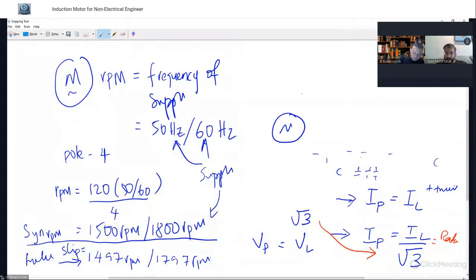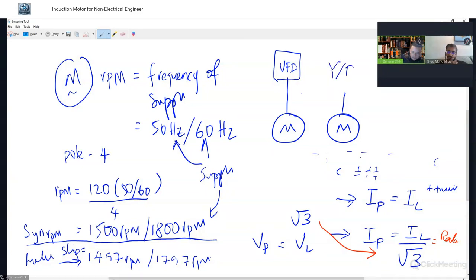Now, if you have motors here, you are going to connect your VFD here, right? Now imagine, the question just now, how are you going to connect star delta and VFD together to the motors? So it's not possible, right? Because the connection over here, the interface to the motor, is actually one only. So you have to connect either to the star delta, which requires 6 connections, but for VFD, we require only 3 connections. That means U1, V1, and W1. Okay, hope that answered the question.